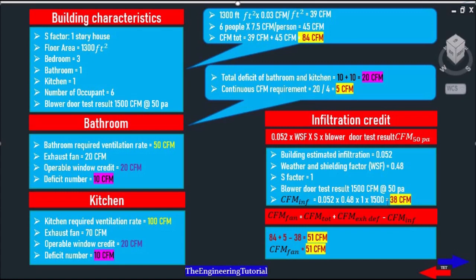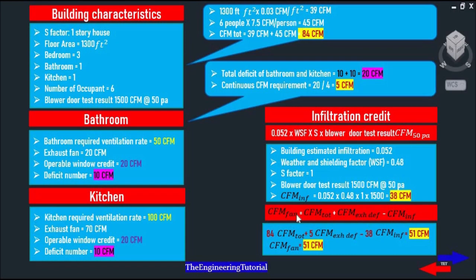That gives us an infiltration credit of 38 CFM and to determine the whole house ventilation fan will use this equation. CFM fan equals CFM total plus CFM exhaust deficit minus CFM infiltration. So if we plug these numbers in we see that comes out a total ventilation rate of 51 CFM. So we need to install a fan that can provide a total continuous ventilation of 51 CFM.